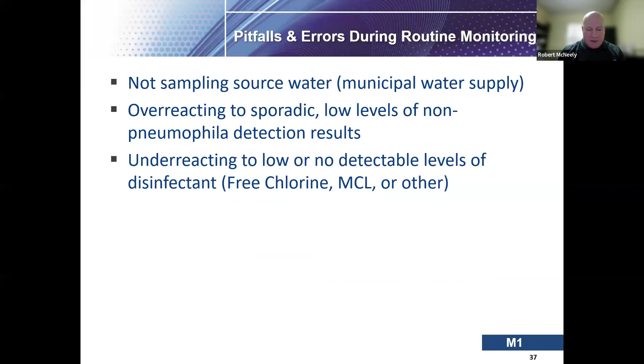Also, not reacting enough to low or non-detectable levels of disinfectant is a problem. That's probably the most important control we have right now - more than heat, more than anything else. If disinfectant is there, the control is generally there. Relying on hot water as a control is a mistake - it's been shown too many times that temperature is not an effective control.